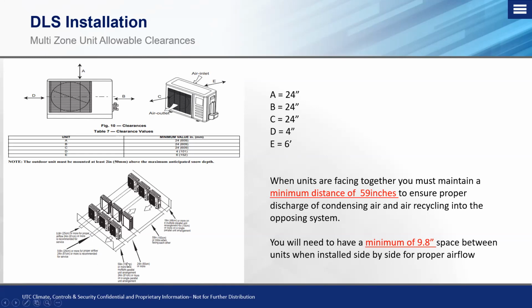Now, when we look at the bottom style, we have a larger ductless application where we have multiple ductless systems. If you have a row of ductless units, in this case, we've got 9 ductless indoor units on this rooftop application. When the units are going to face each other, so we have the condensing fan motor on this system and the condensing fan motor on the opposite system pointing in the same direction, you must maintain a space between those two condensing fan motors of 59 inches to ensure proper discharge air from that outdoor unit.